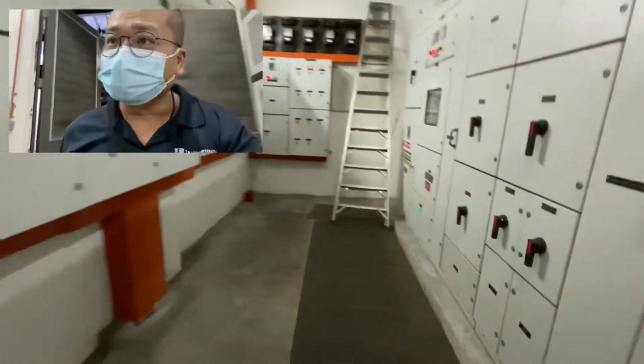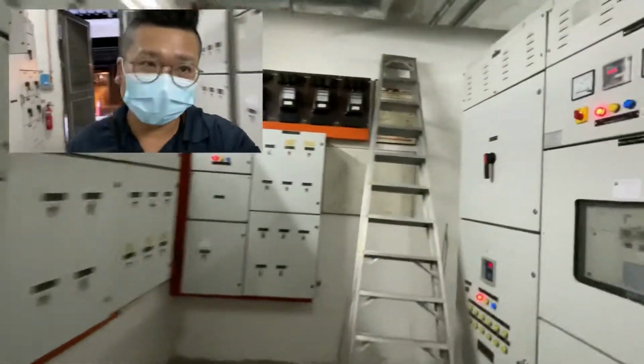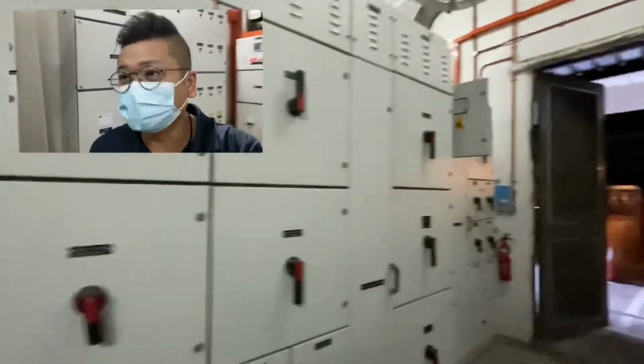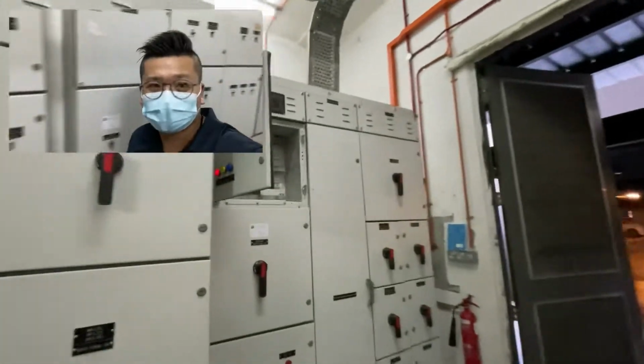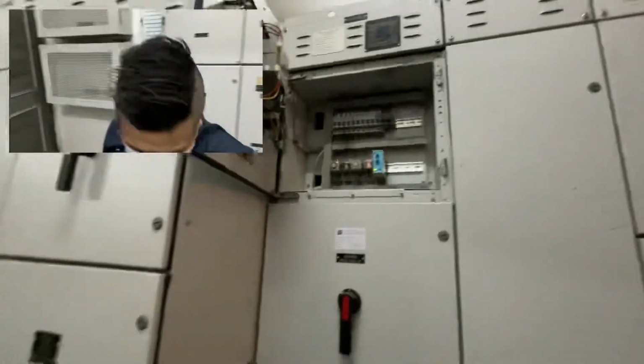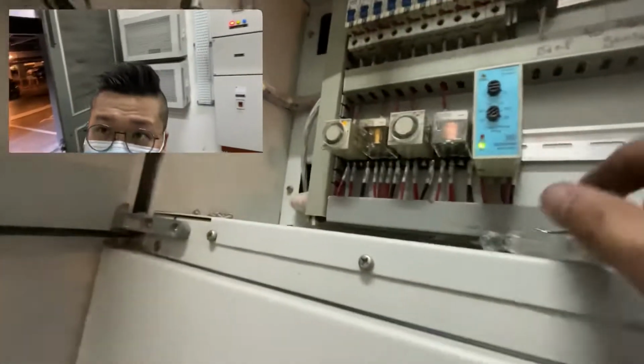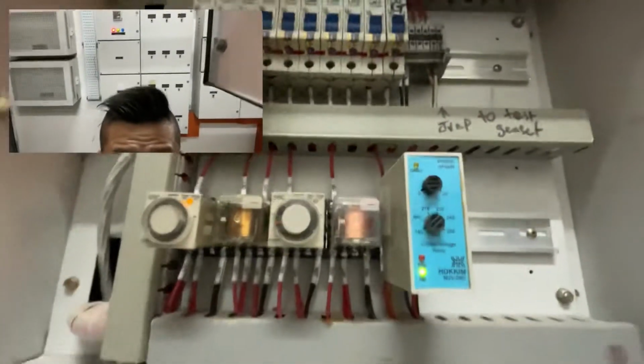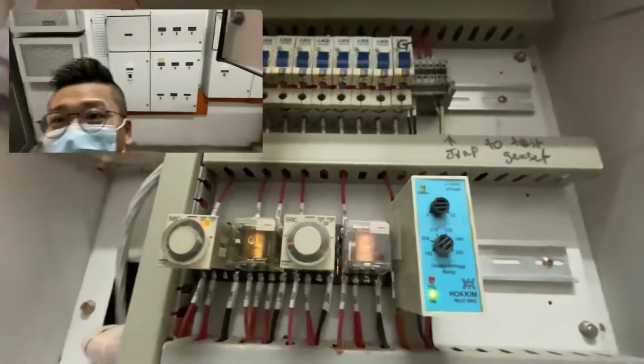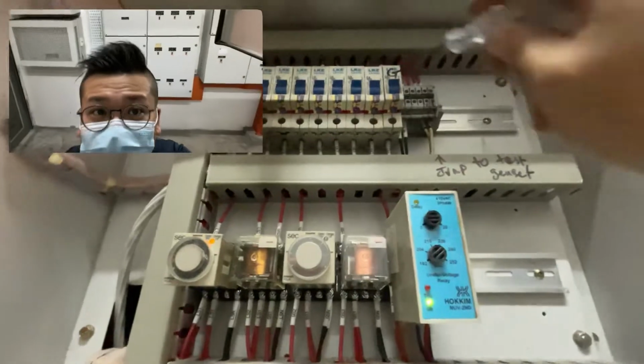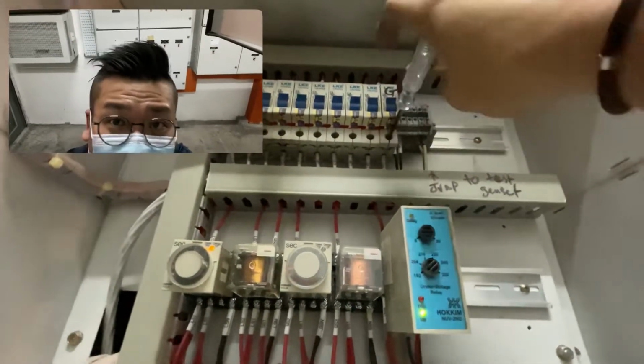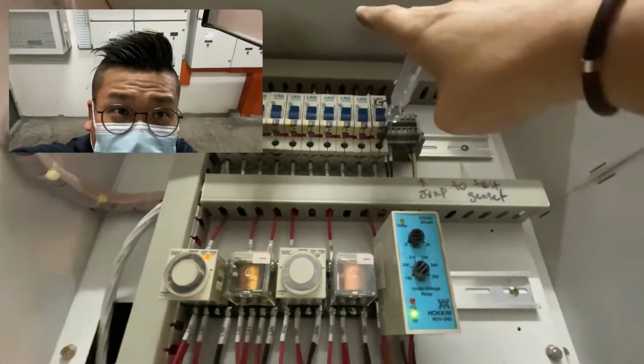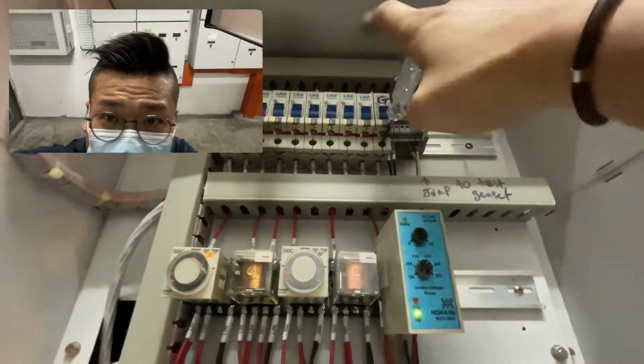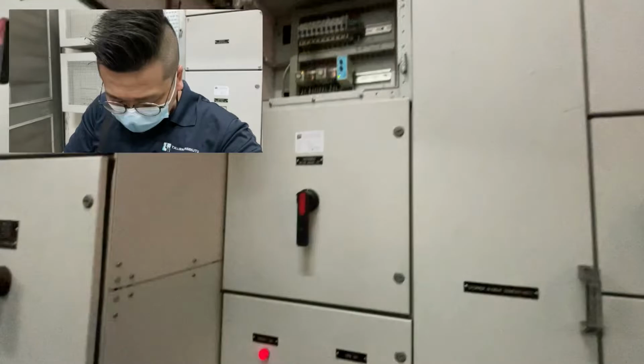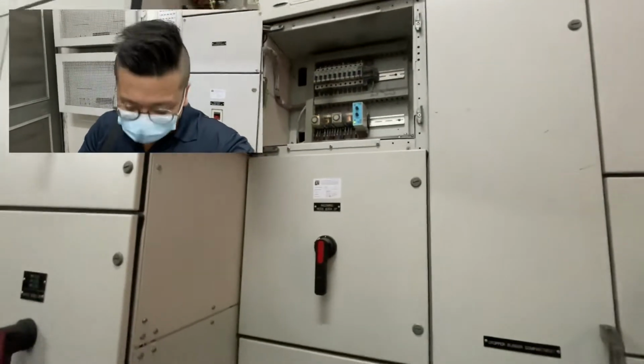Okay, so from here we're going to run the genset by simulating a TNB power interruption signal. Just like previously we have done at block 2, now we do it on block 1. So this is a genset supply. Currently the genset is not running, so there's no voltage here. So now I'm going to jump the signal and allow the genset to start automatically from here.